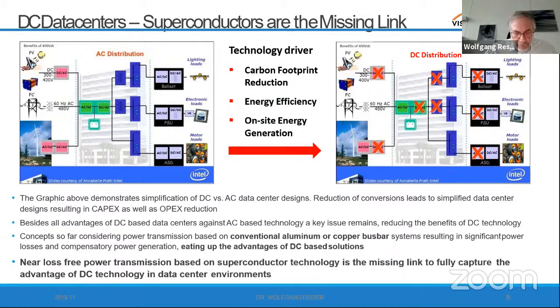Another area we think is very important is data centers. Superconductors are the missing link there. Why? More than 10 years ago, studies were done by Intel about using DC for data centers. In the meantime, more than 25 data centers worldwide are running on DC, but as they get larger, the current is larger, and the current losses on copper or aluminum bus bars or cables eat up the higher efficiency of DC. So superconducting technology is the missing link to capture the advantage of DC technology in data center environments.